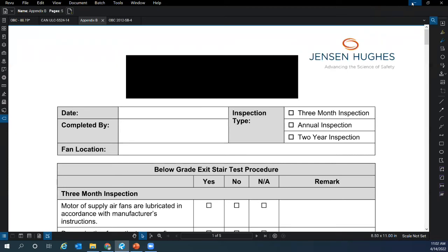But essentially, if you have a 20-story building and you're looking at, let's say, stairwell A, you're going to have readings on all stories. For example, if we have a pressurized stairwell, you're going to have a pressure reading using the manometer that Ali showed earlier. You're going to have a pressure reading on the corridor side and on the stair shaft side on each floor, showing the pressure differential. And then certain companies like Jensen Hughes, for example, will also take the door opening force readings on each story as well. And then you'll have a table for stairwell A, a table for stairwell B, a table for the pressurized elevator shaft, and so forth. Yeah, exactly. So all that should be there.